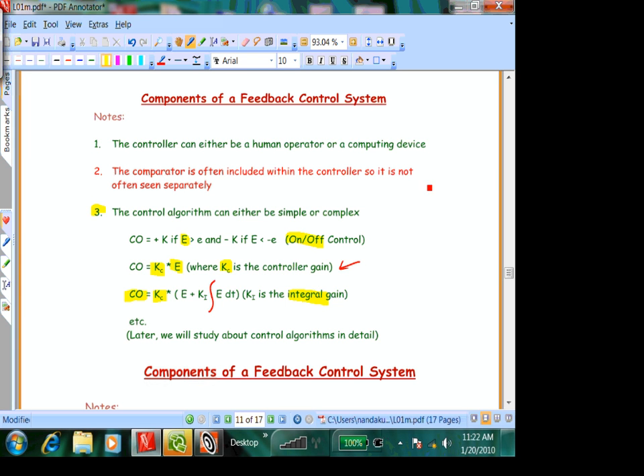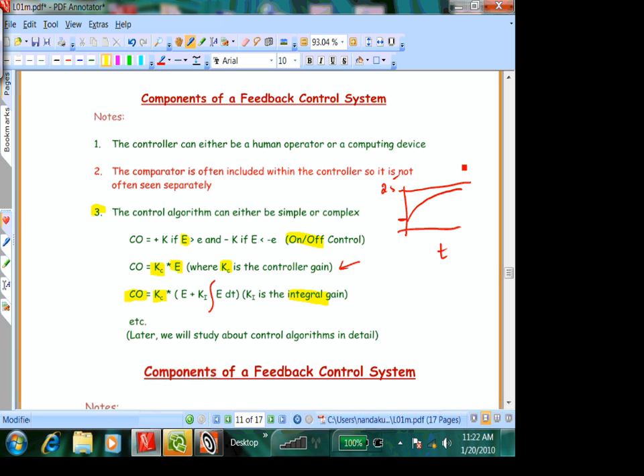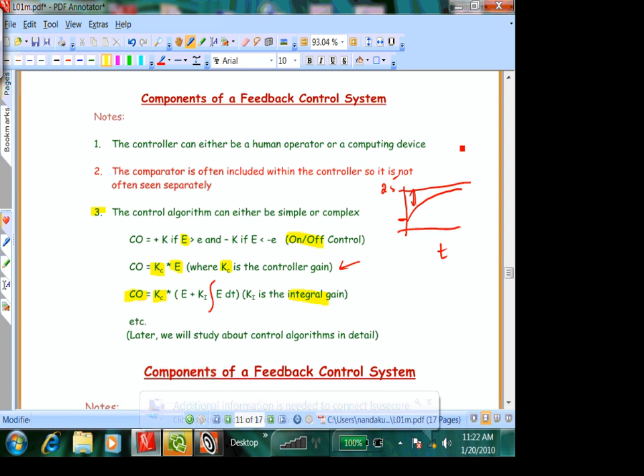So in the second case, we are saying that the controller decision depends only on the current error. Okay? So if you plot, for example, time, and this is the set point, say the temperature is 25 degrees, and this is the actual temperature. Initially the temperature was 23 degrees, it is going towards 25 degrees. So what will be the error? The error will be the difference. The proportional controller says the amount of fuel that I'm going to burn at any instant of time is simply proportional to this vertical distance, the error. So as the error becomes smaller and smaller, the valve gradually shuts down a little more, until when it reaches 25 degrees, the valve is completely shut. Okay, so that's what a proportional controller does.